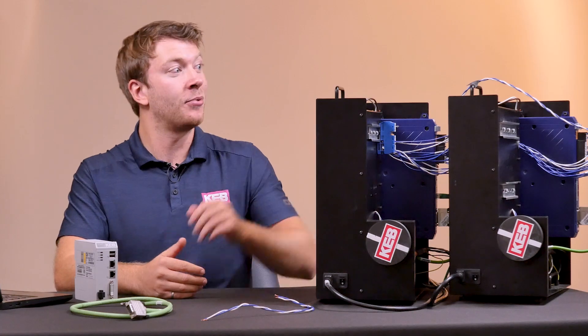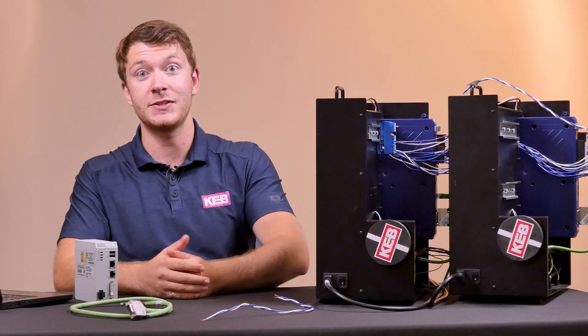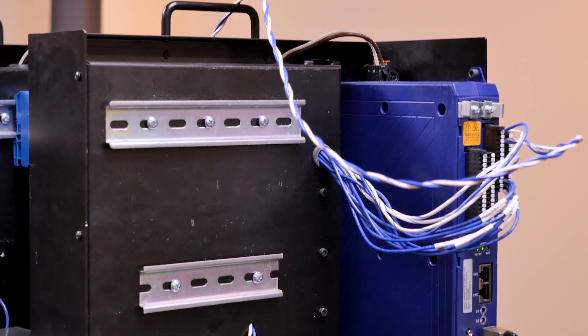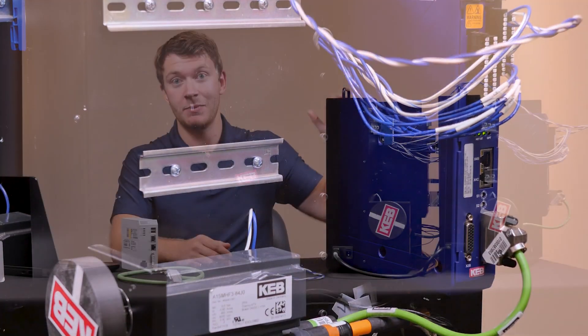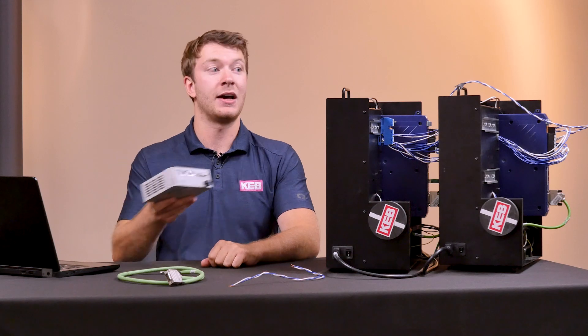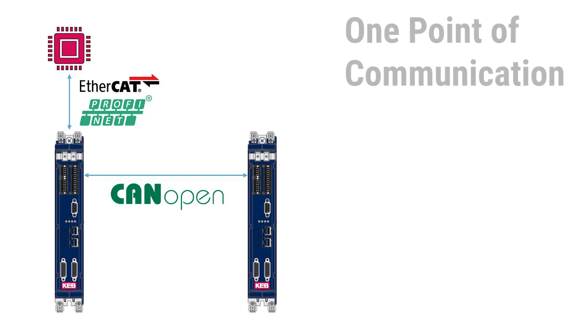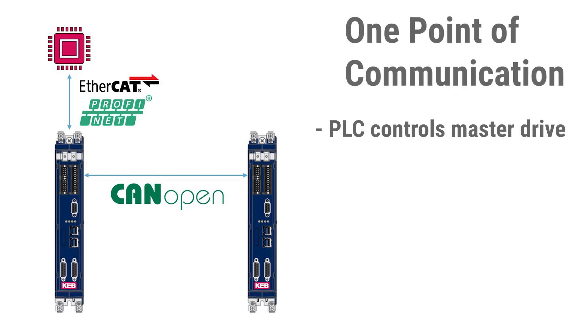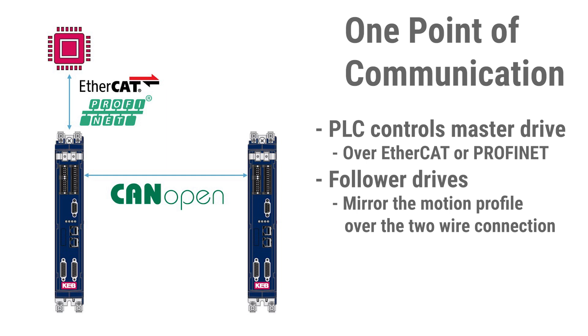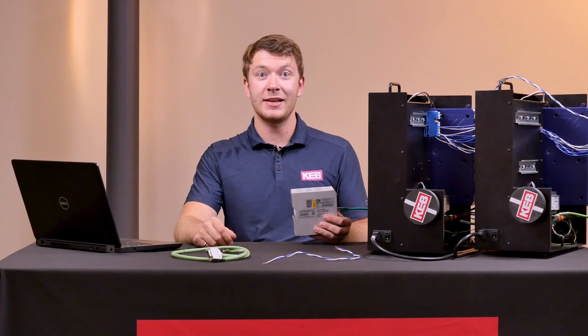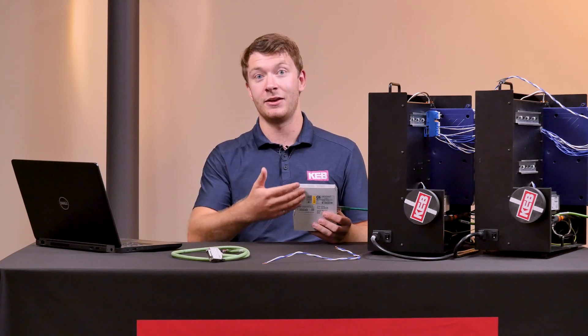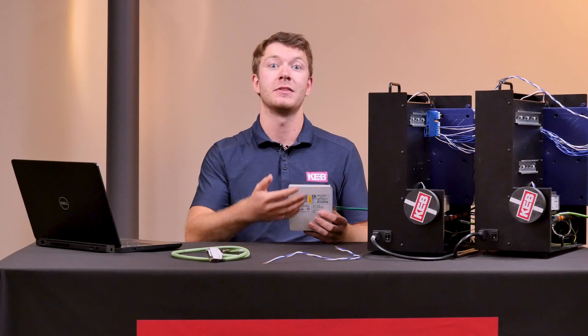CAN cross-communication can operate as its own independent field bus, but it also doesn't have to. Two drives can communicate with each other over CAN cross-communication while a PLC talks to the master drive over EtherCAT or PROFINET. The PLC can then control the master drive over this link, enabling a more sophisticated motion profile, and the follower drives mirror that motion profile over just the two-wire link. This allows several tasks that would otherwise be handled by a PLC to be offloaded to the drives.